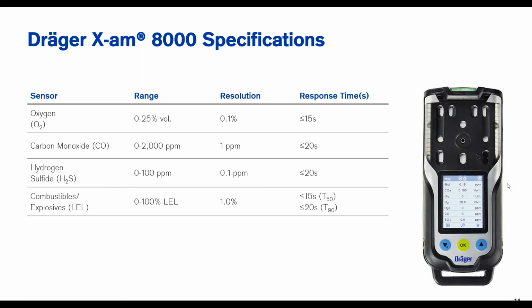And to focus on that T50, T90 while we're here, what that actually means is, more or less in a nutshell, how long does it take to get a 90% accurate reading based on your environment? And so I need to give that sensor within that meter time to send it through that catalytic bead sensor. I need to give it time to have that actual reaction and produce that reading on my display. It's not instantaneous. Now, even though 15, 20 seconds may sound like a little bit of a wait.